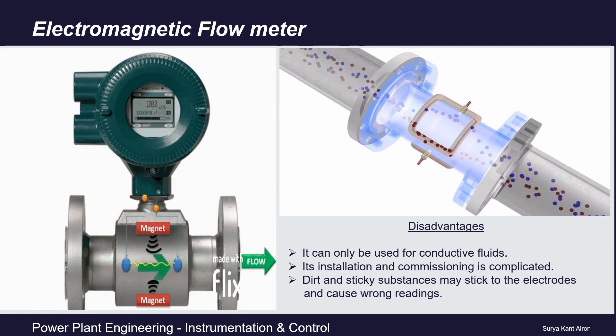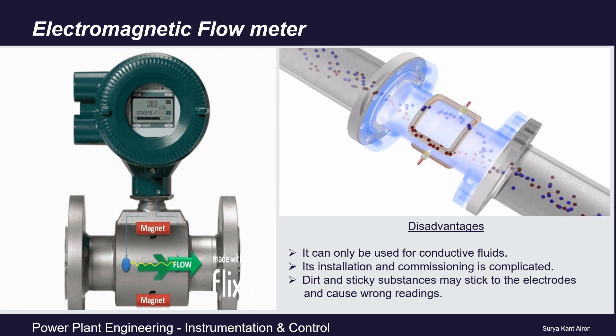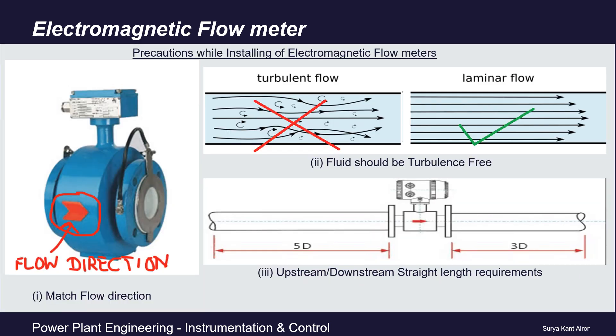Installation and commissioning is complicated, so a few precautions must be taken. First, check the flow direction — check the arrow sign on the flow meter. As seen in the figure, there is a mark on the flow meter: the tail of the arrow is the upstream side and the head is the downstream side. The flow direction shown on the flow meter must match the process flow direction; if connected in reverse, readings will not be accurate. Second, the fluid should be turbulence-free — it works best with laminar flow.